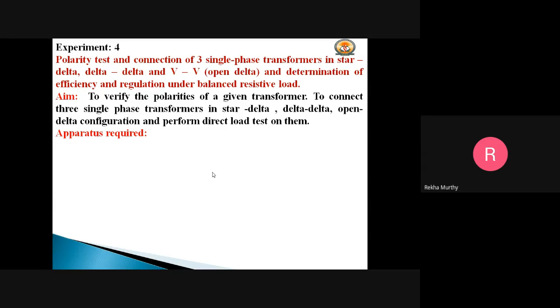Before we go into that, why do we conduct this experiment? Why is the polarity test required? It is necessary to know the relative polarity of the primary and secondary terminals at any instant, for making correct connections when two transformers are connected in parallel to share the load on a system. That is why we conduct this polarity test.